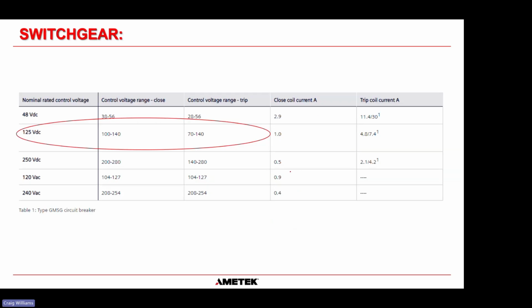Now, for switchgear systems, this is actually a table from a type GMSG circuit breaker. This is where the load tolerances come in. So for the nominal rated control voltage of 125 volts DC, they're saying for the closing circuit and the trip circuit, you have to operate within these ranges. And for a 125 volt DC system, they're saying that their tripping and closing circuit will only operate between 100 and 140 volts DC.